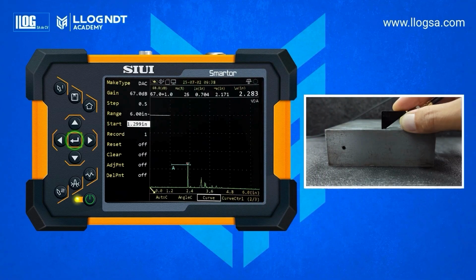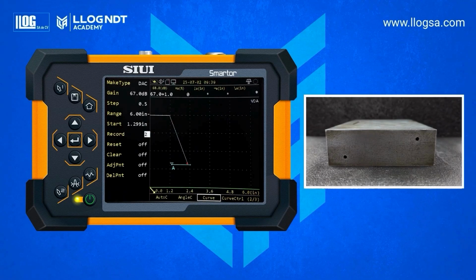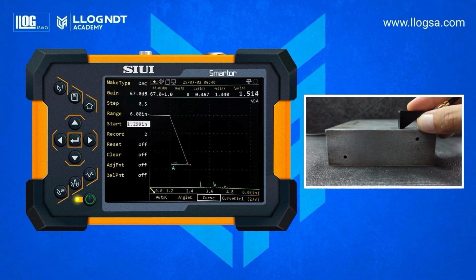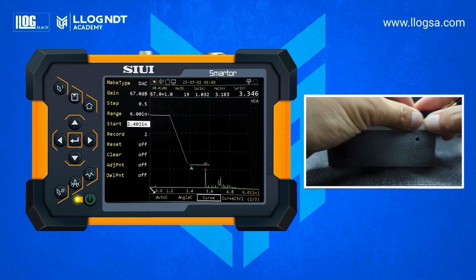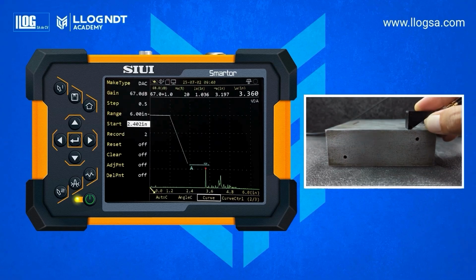Without changing the gain control, press Enter to save the second point. Finally, aim the transducer at the hole located at 3/4 of the thickness, 3/4 T. Place the gate over the corresponding echo and move the transducer back and forth until the maximum amplitude is found. Once located without adjusting the gain, press Enter again to store the third point.